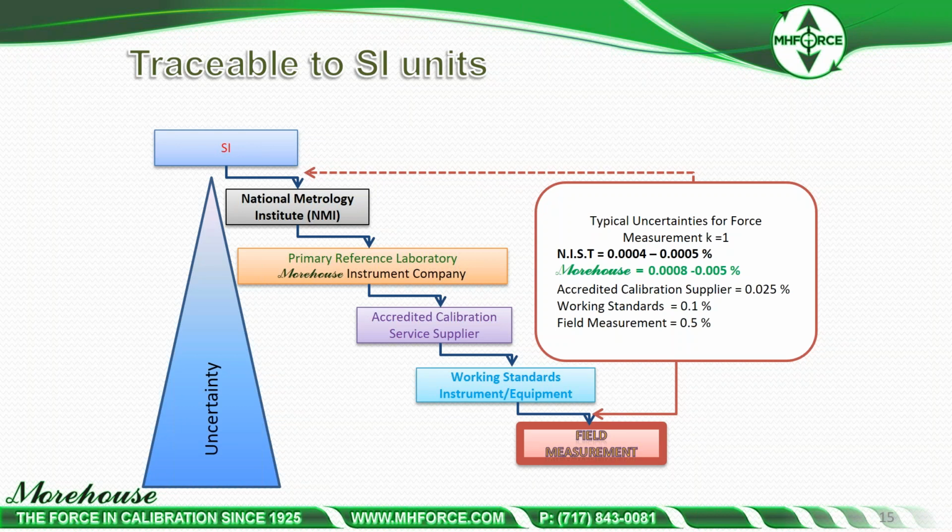So essentially, this is what it means, traceable to SI. And if you notice this, the uncertainty gets larger the further you are away from the true SI unit, or the further away you are from the NMI.